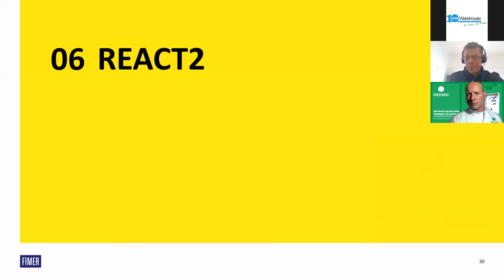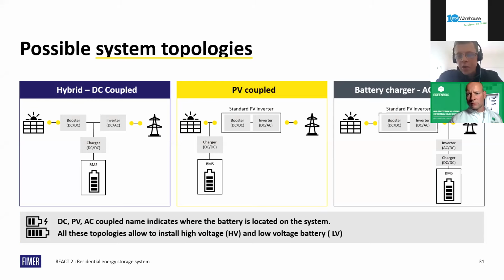So I'll move on to the React 2, which is the 3.6 and 5 kilowatt inverter with built-in modular batteries offered by FIMER. Before I dive in, I'll cover some of the topologies of battery systems: DC coupled, where the battery is connected on the DC side of the inverter; PV coupled, where the DC batteries are connected with the array; and AC coupled batteries, which is ideal for retrofit situations where you have an existing system and connect batteries for storage on the AC side. The React 2 can offer the DC coupled and AC coupled solutions.